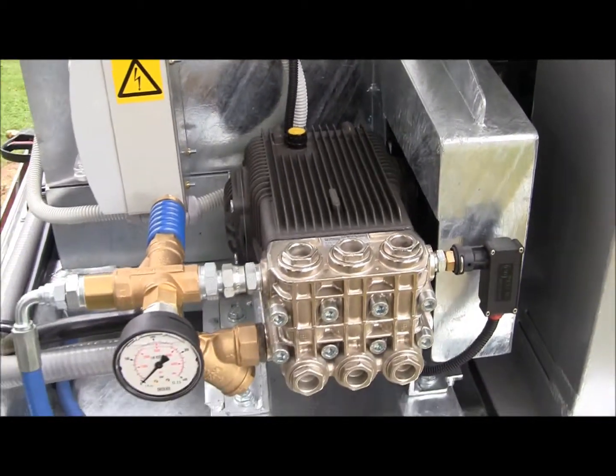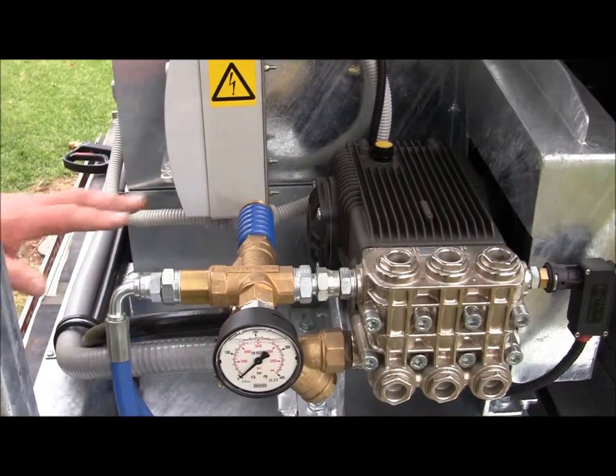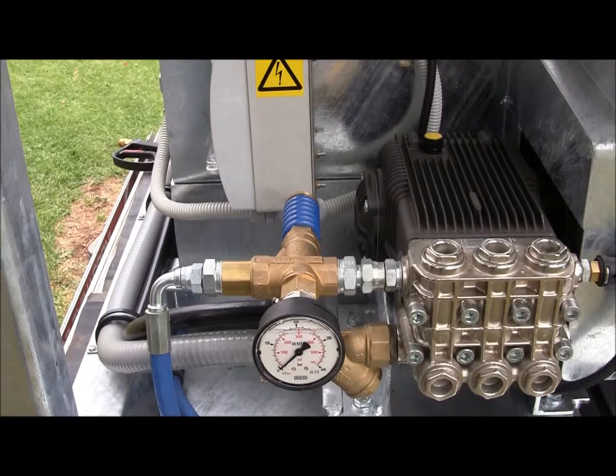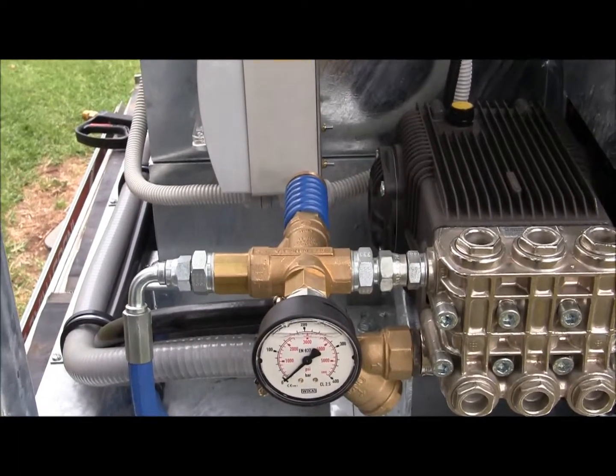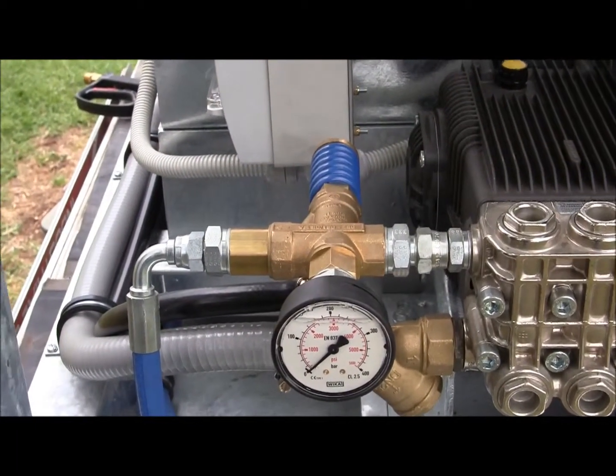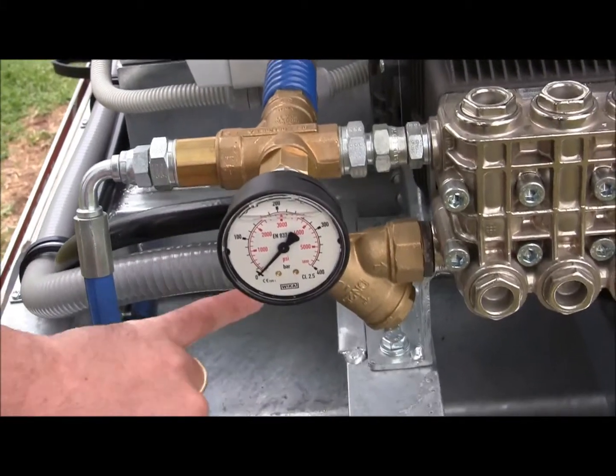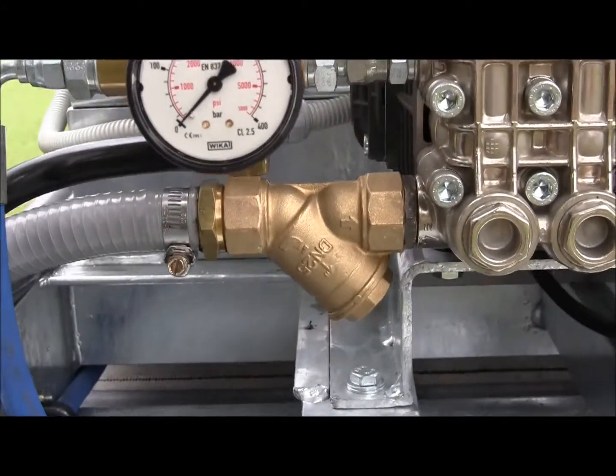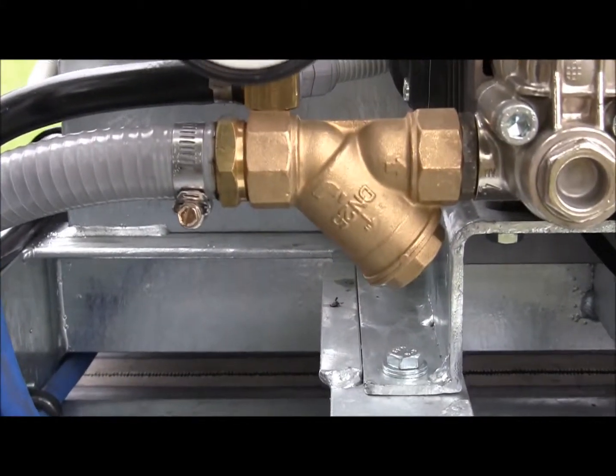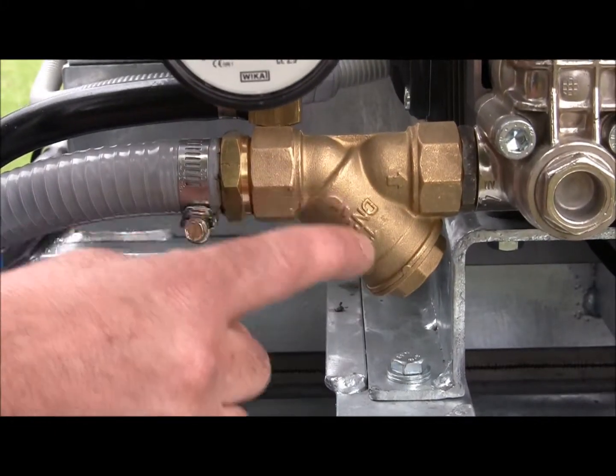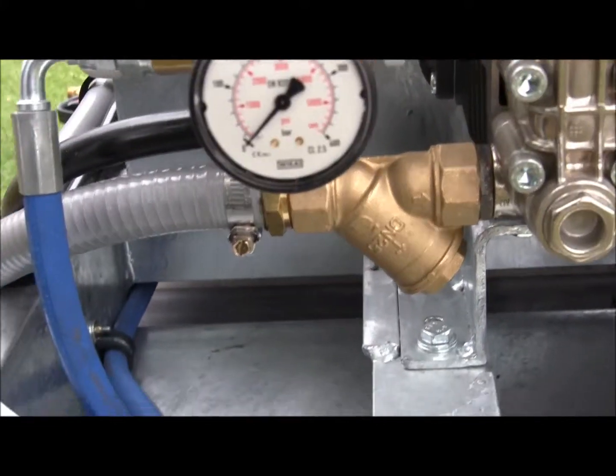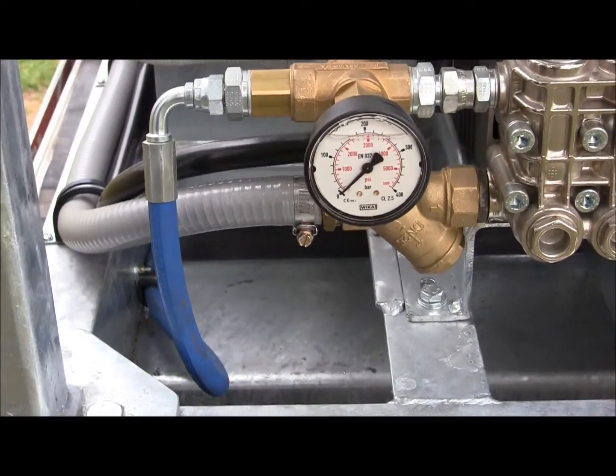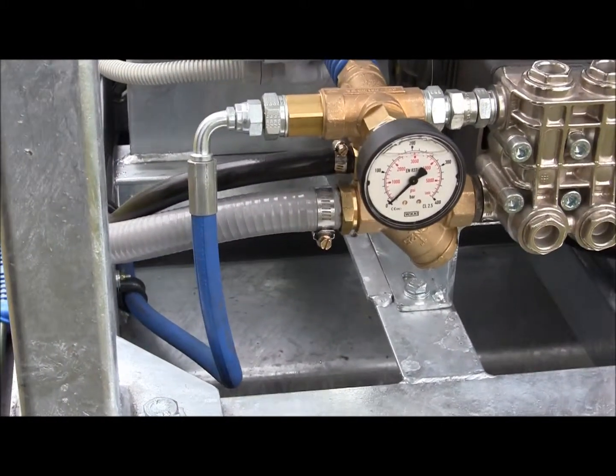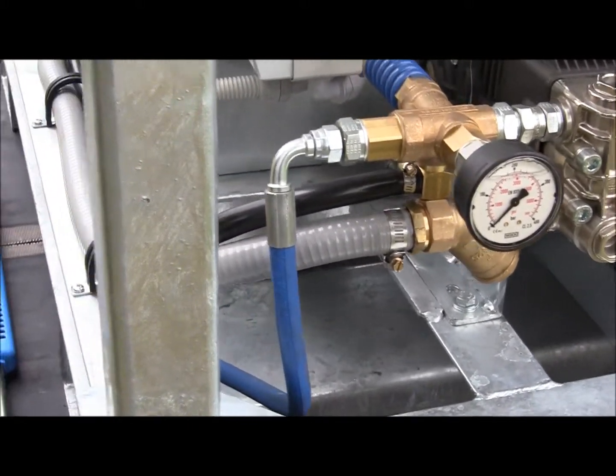Down here off the side of the pump we have the blue spring on the Italian made bypass valve with the glycerine pressure gauge showing the working pressure off the unit. And directly below the pressure gauge we have a brass Y strainer. This is for filtration of the water inlet. It has inside the brass Y strainer a stainless steel mesh filter, with easy access to drop the bung plug out, remove the Y strainer mesh and clean it and away you go.